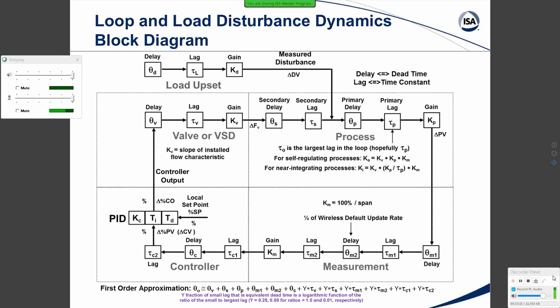And then you have the process, and you've got dynamics, and there's usually more than one delay and more than one lag. Here we're simplifying delay to being dead time and lag to meaning time constant. We've got usually at least two different sources in the process of that. It could be due to mixing, it could be due to injection piping or dip tubes, or it could be due to thermal lags and delays and lags associated with the coil or jackets, and we have a process gain. Then we have to measure that, so we have a delay associated with the measurements, maybe often a couple of them.